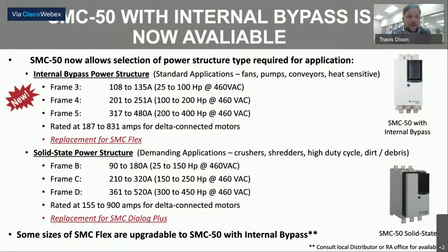These are the frame sizes offered for the internal bypass and solid state units. Anywhere from 108 amps to 480 amps for line connected motors, and from 187 amps to 831 amps for delta connected motors for the internal bypass. And it's really geared more towards the replacement for the SMC Flex, you know, later on down the road, when this is going to be the foot forward of the SMC 50.